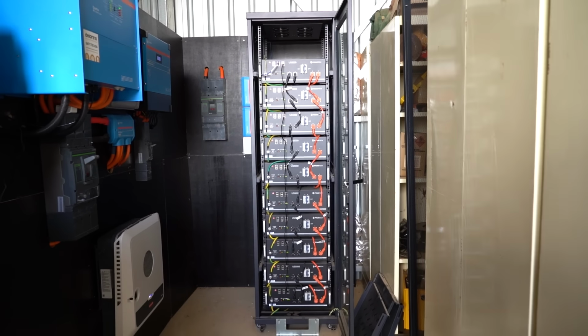We've got about 15 kilowatts of solar teed into these big RS450-200 units from Victron, the biggest MPPT they have in their range. That's going to provide a lot of DC coupled charging, so if for whatever reason the batteries died and we had no charge, we can black start this system straight up in the morning with a bit of DC coupled charging.